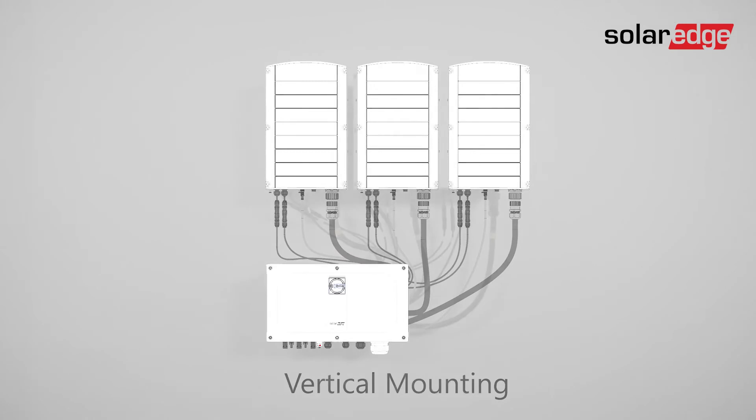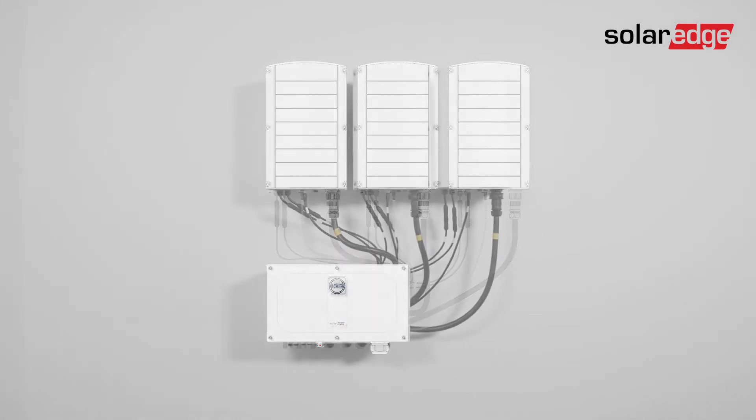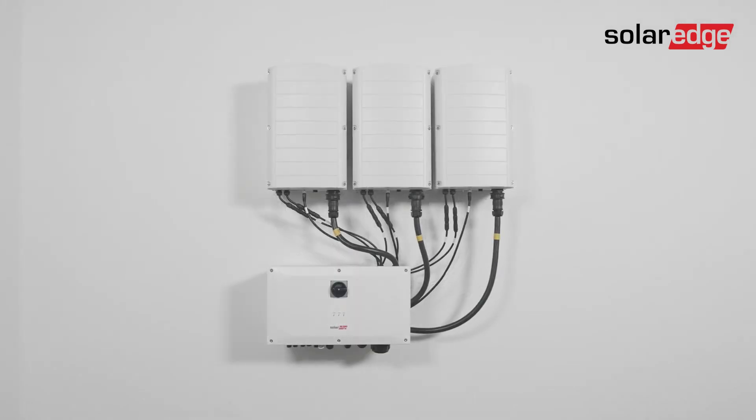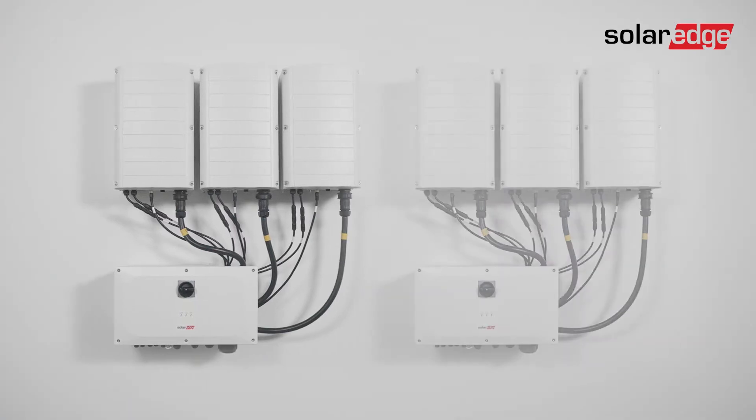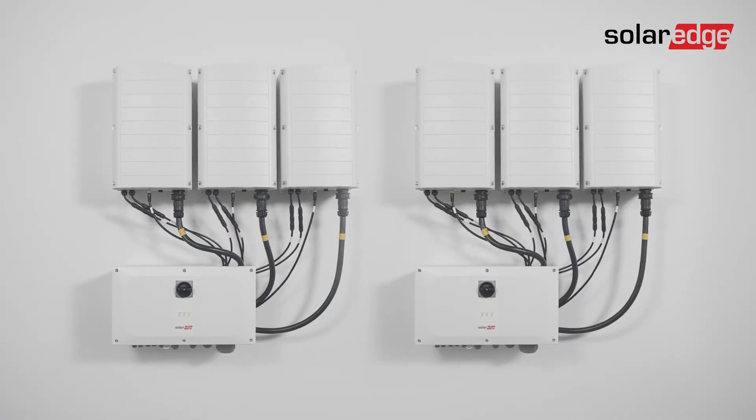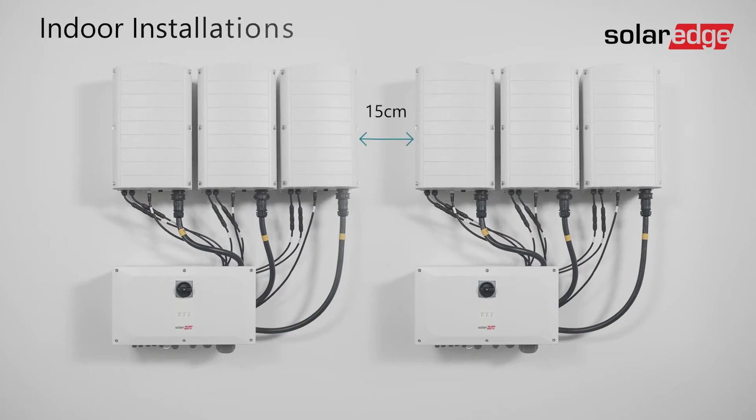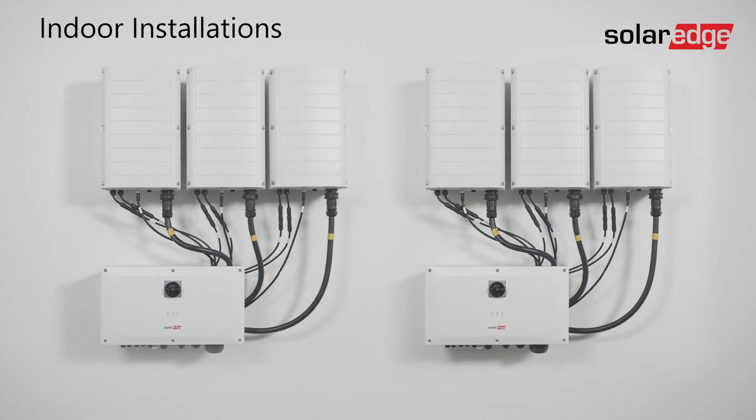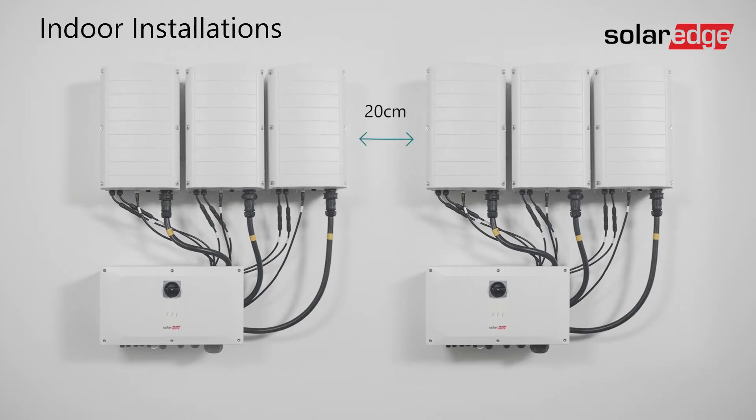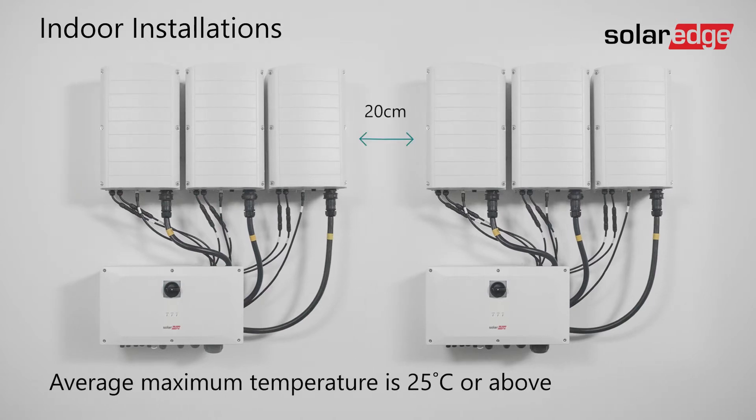When planning the inverter's installation location, consider the minimum clearance distance required for proper heat dissipation. If you plan to install multiple inverters in a row, the clearance distance between the inverter side should be at least 15 centimeters for indoor installations. Note that the minimum clearance distance increases to 20 centimeters if the average maximum temperature in your location is 25 degrees Celsius or above.